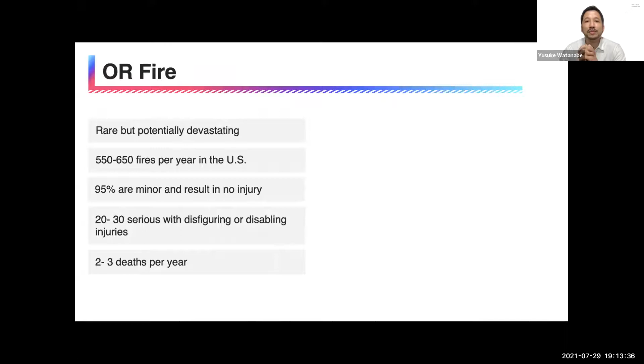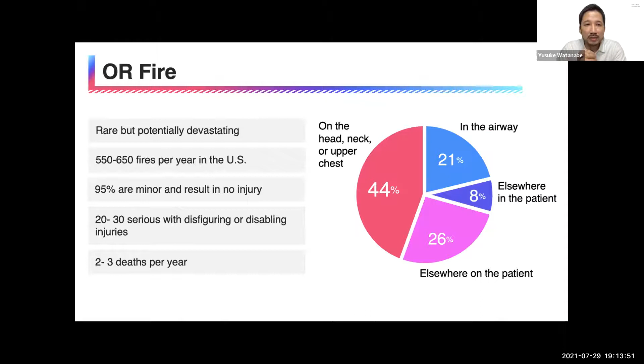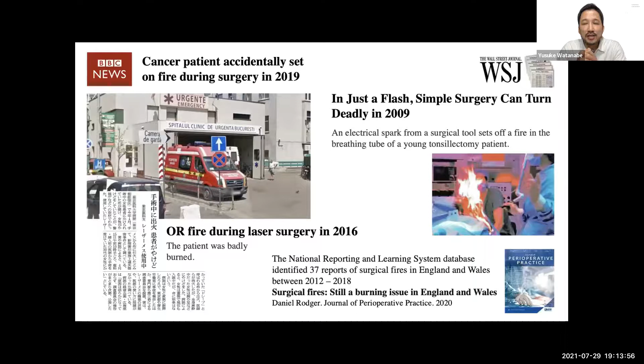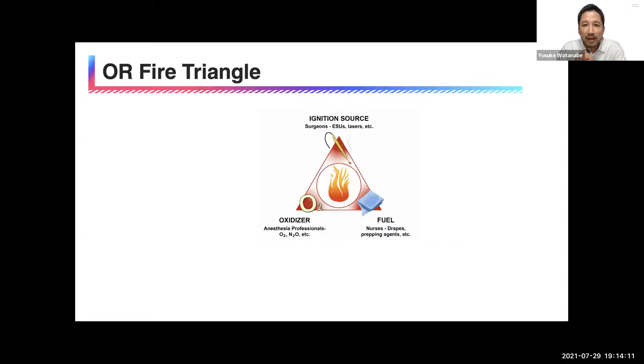About 20% of fires occur in the airway. There are a lot in the upper chest, head and neck area, largely due to oxygen escaping underneath the drapes. Here, these are reported cases across the world. This is a really global problem. We should remember the fire triangle that consists of 3 elements: ignition source, oxidizer, and fuel. Ignition sources can be electrosurgical units for 70% or lasers for 10%, and other surgical devices such as fiber optic light sources.